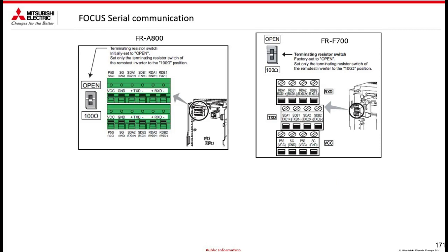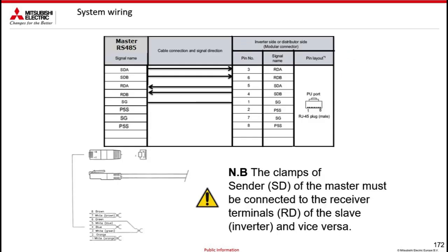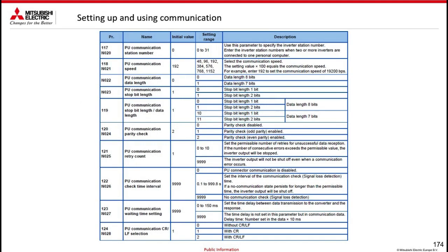The previous version of the FR-A800 had this plugin that allows communicating with a master, which can be, for example, a Mitsubishi Electric PLC with the Mitsubishi protocol, and commanding it. So, as you well know, serial communication obviously requires parameterization, such as the station number, the baud rate, the string type, so the number of data bits and the stop bits, the parity control, and possibly the communication waiting time, the CRLF control, and of course the protocol selection. I won't dwell on this topic too much.